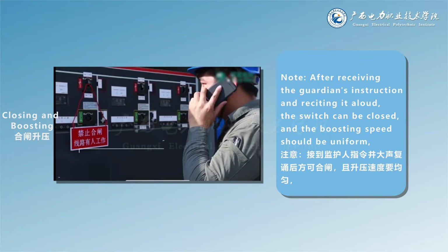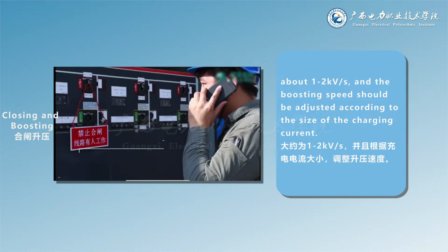Note, after receiving the guardian's instruction and reciting it aloud, the switch can be closed, and the boosting speed should be uniform, about 1-2 kV/s, and the boosting speed should be adjusted according to the size of the charging current.